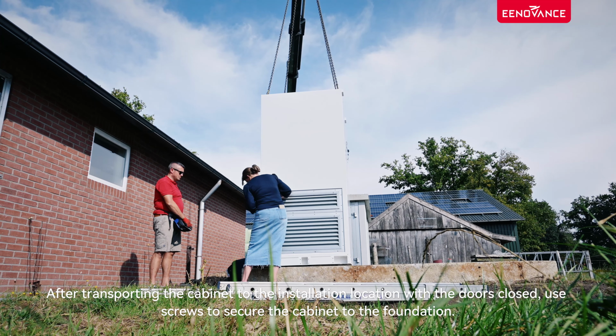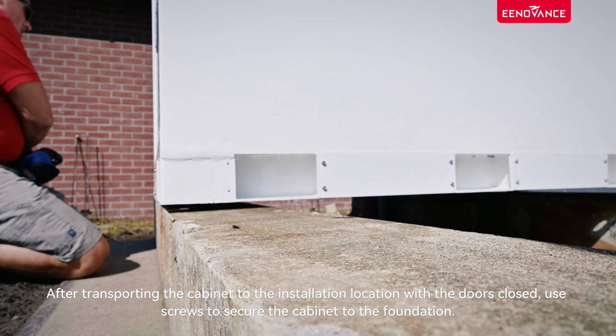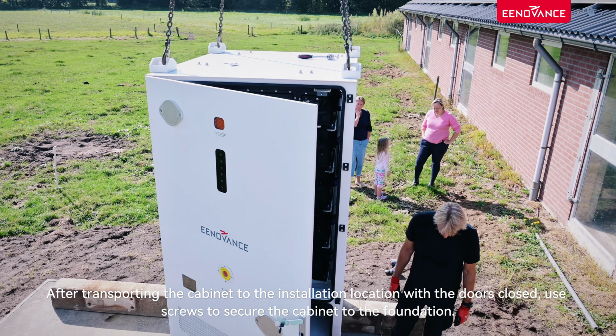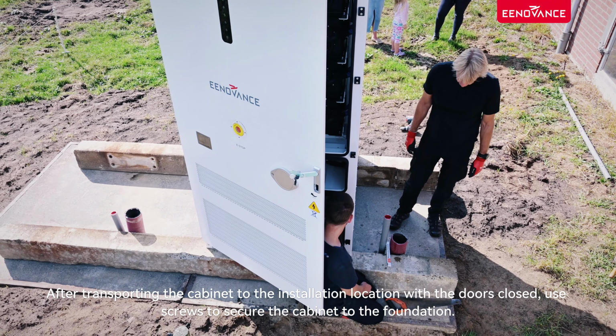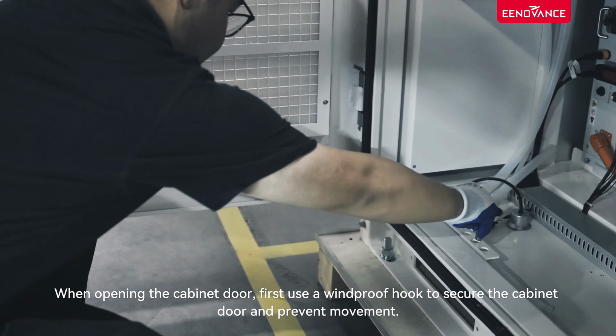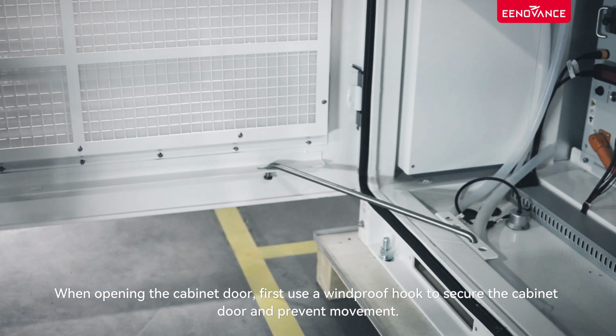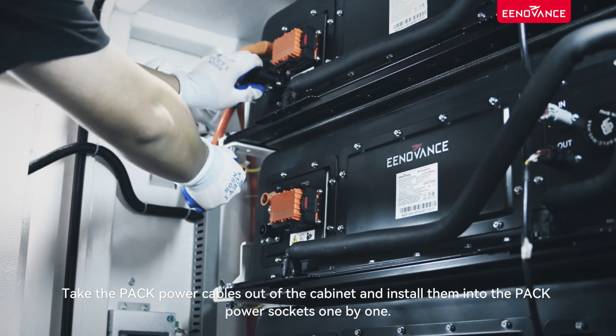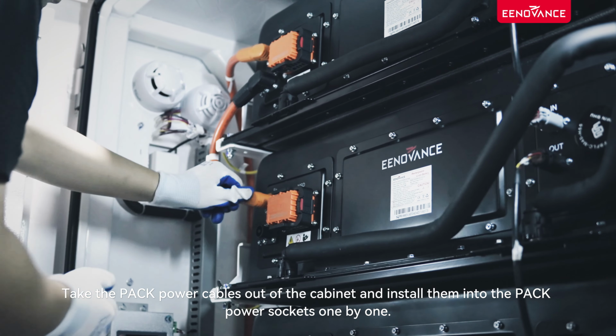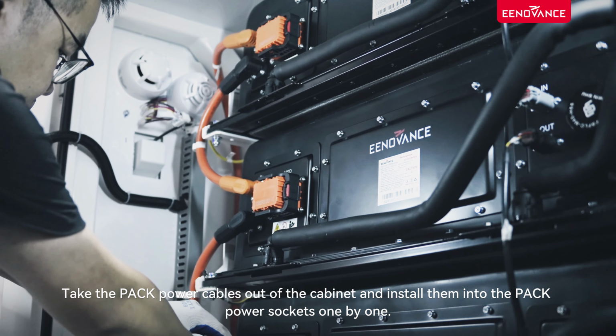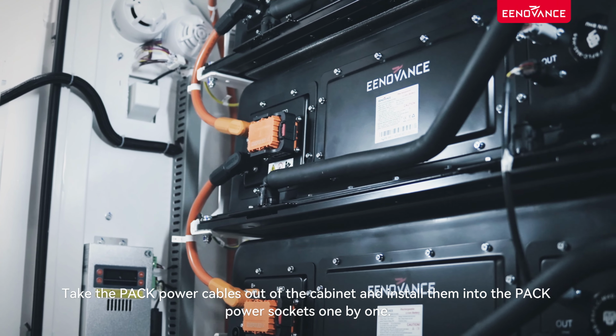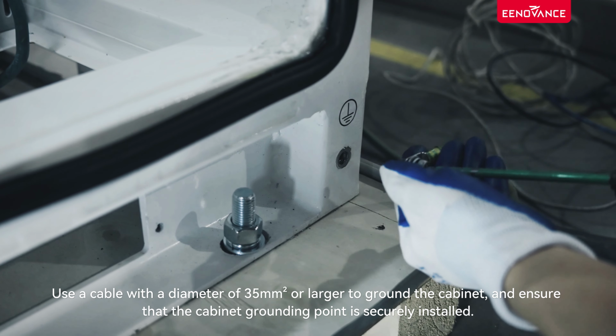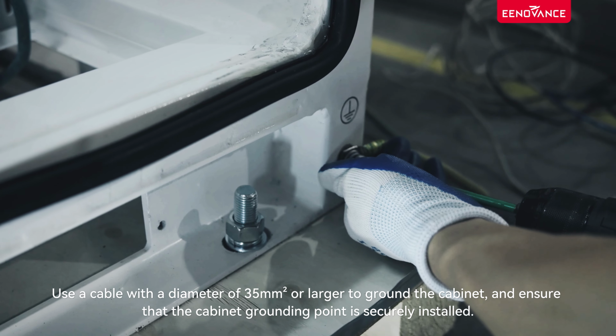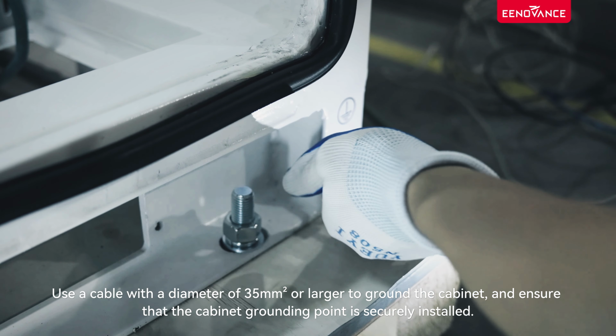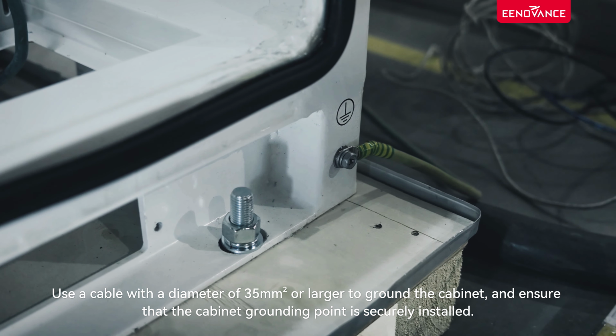After transporting the cabinet to the installation location with the doors closed, use screws to secure the cabinet to the foundation. When opening the cabinet door, first use a windproof hook to secure the cabinet door and prevent movement. Take the pack power cables out of the cabinet and install them into the PACK power sockets one by one. Use a cable with a diameter of 35 square millimeters or larger to ground the cabinet, and ensure that the cabinet grounding point is securely installed.